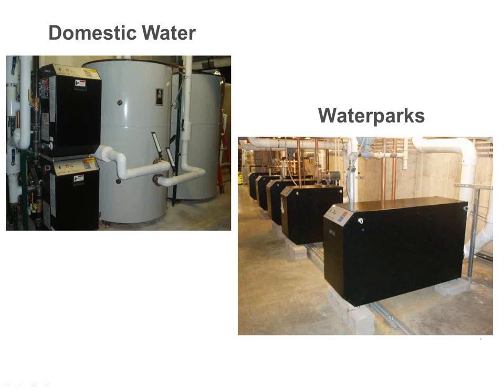High efficiency boilers also love water parks. Think about it. What do you got? You got 75, 80 degree water coming back to the boiler. It's always in condensing mode. Really nice application. Both of them are good applications when we help you engineer them correctly.